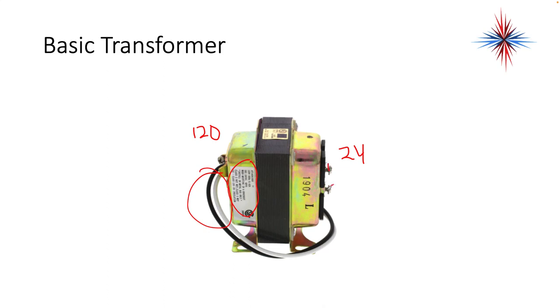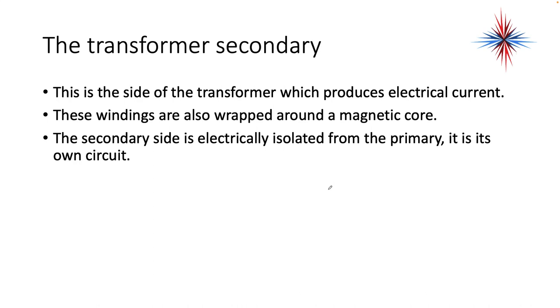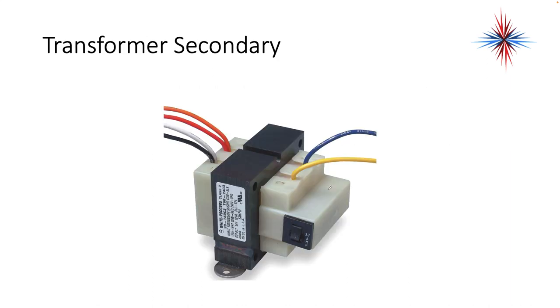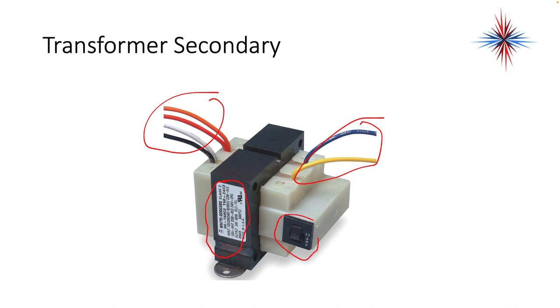There are two screws here that are my secondary side. The transformer secondary is the side of the transformer which produces electrical current. These windings are also wrapped around the same magnetic core. However, the secondary side is electrically isolated from the primary — it's its own circuit. I should never be able to take a resistance reading between the primary and the secondary side. In this case, the secondary is the yellow and the blue wire coming off the transformer. This transformer also has a breaker on it at 3.7 amps, so if my secondary gets a short, the breaker will pop and it won't blow the transformer.